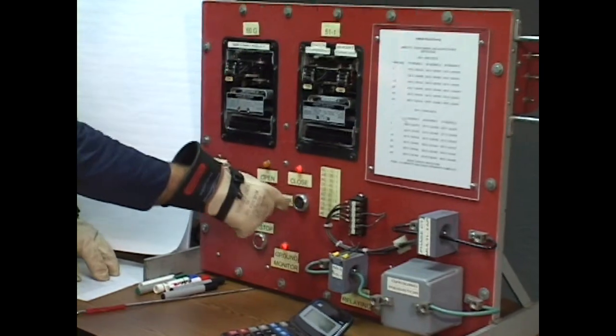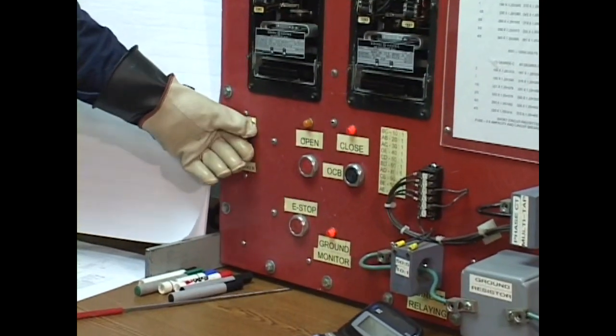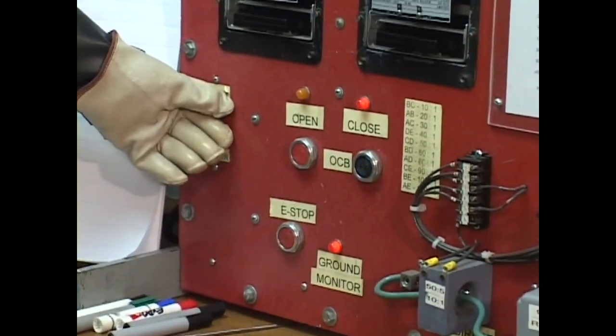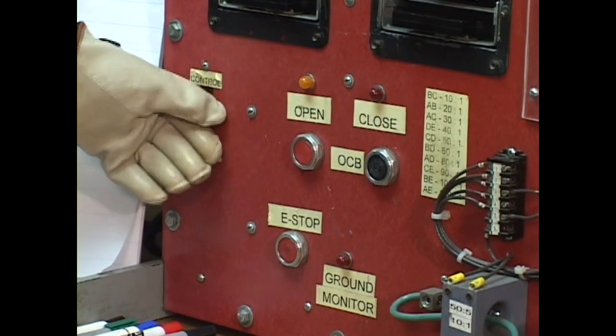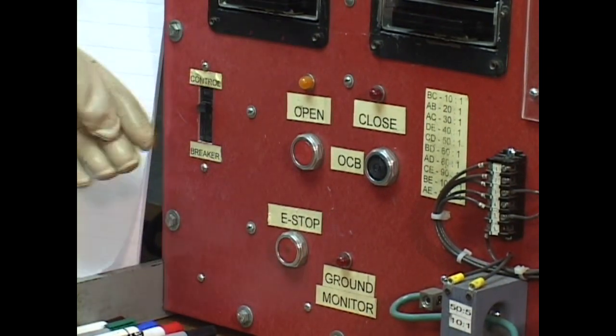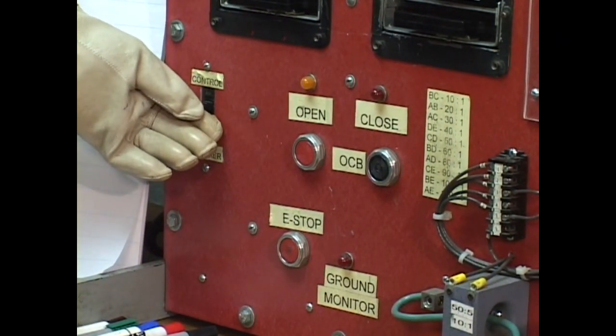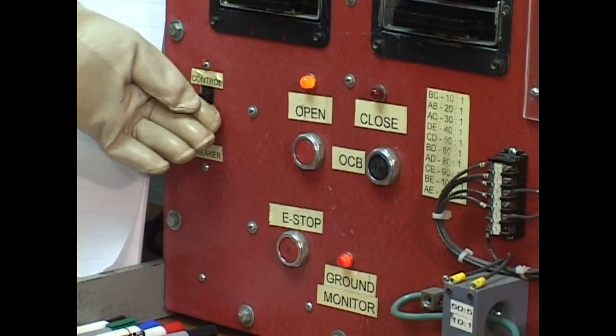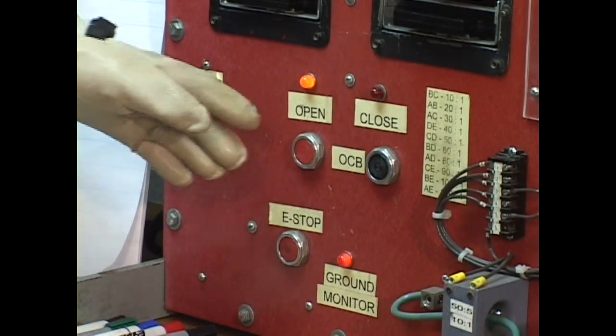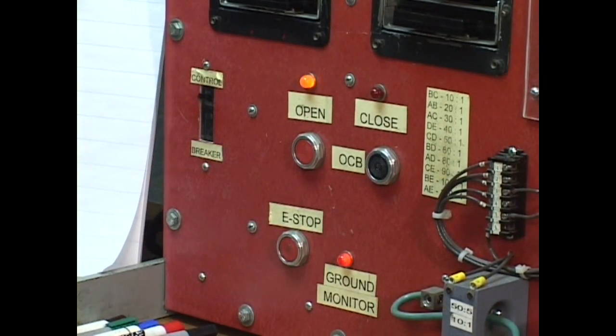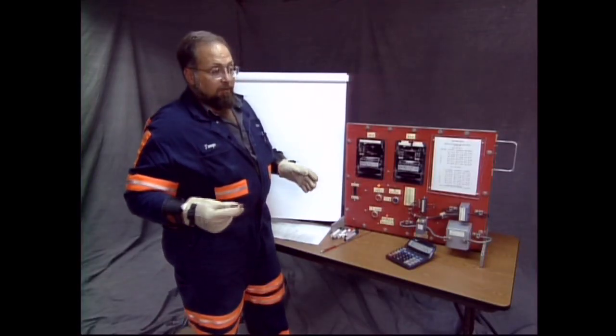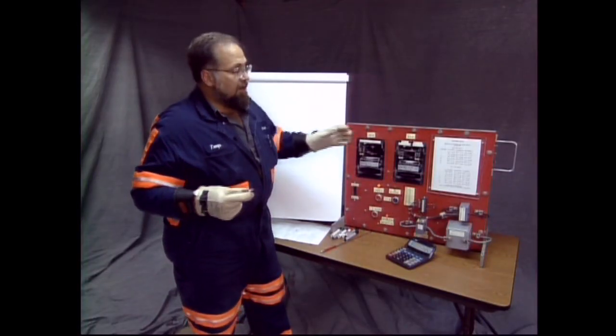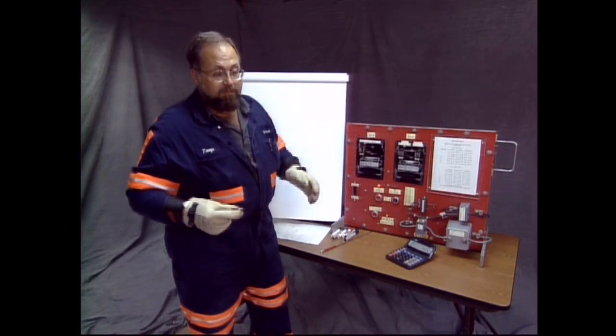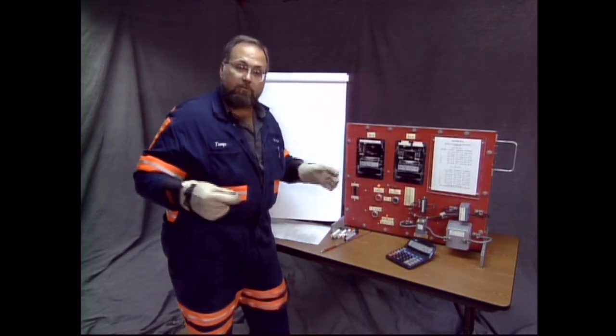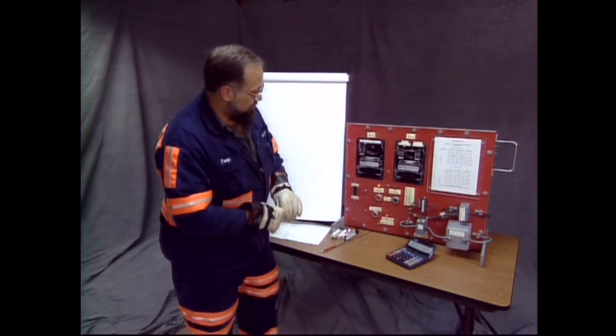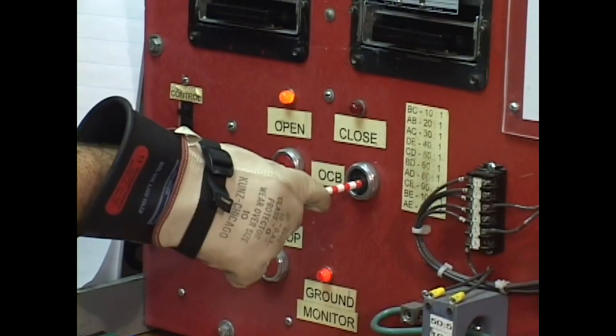You have your breaker closed, your OCB is closed. You manually operate your control breaker. Now, all the lights go off and the breaker has fallen. So you reset your control breaker. The OCB is in an open position. And that proves that you had under voltage protection. Under voltage meaning that if I have a loss of my line voltage 40 to 60%, by definition, the OCB should fall. And it did. That's good. So let's reclose the breaker.